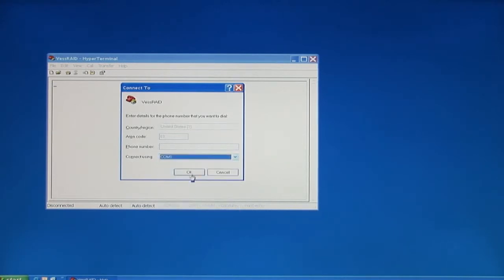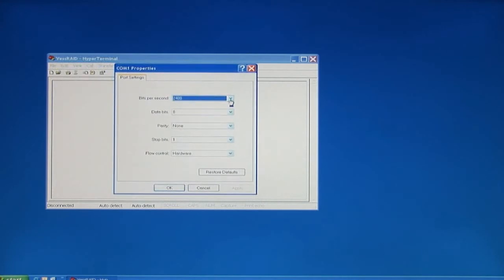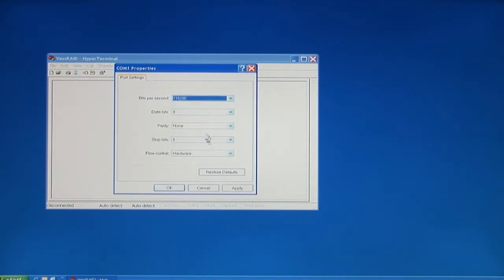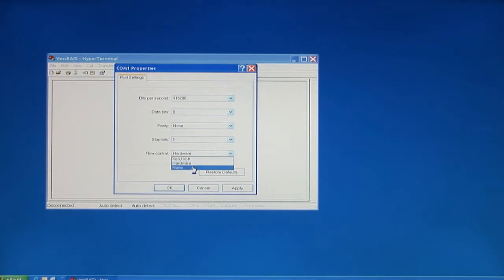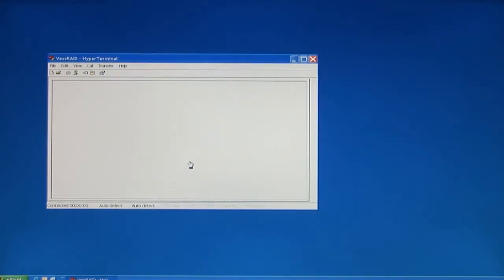I'm using COM1 through RS232 to talk to the host, so we'll have to configure COM1. You're going to see 115,200 as the bits per second, 8 data bits, parity none, stop bits 1, and flow control none. Click OK, then we'll enter the dialog window to log in.